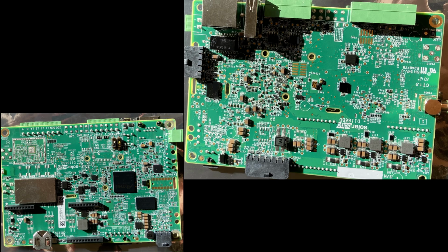Now, I've seen this in shipyards, in equipment rooms, and I've seen this in industrial sites. It's common to happen during commissioning. Someone's wired up the wrong cables to the wrong piece of equipment. There's no such evidence of this. I've taken photographs on the front and the rear of this, and the board is in pristine condition.